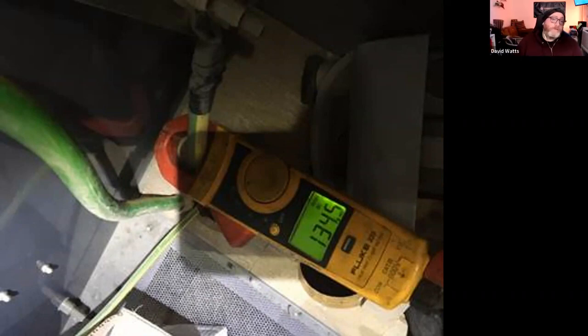I had a chap working with me who was connecting a 16 mil bond onto an earth bar. As he attached that, he got a visual big bang, like a big flash. The big flash, yeah. With the big flash, that's obviously going to give you the pressure wave and that blast. The main concern is the selectivity requirement and the coordination upstream with regards to time. If it's quick and instantaneous, it's just one thrust. This was a bond, an earth bond, which we didn't expect to be charged. If you have any delay in your disconnection, that's where you're going to have significant burns and significant damage. But it could actually be a small flash.